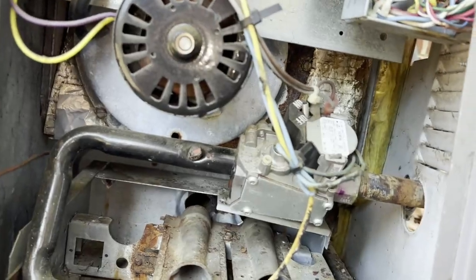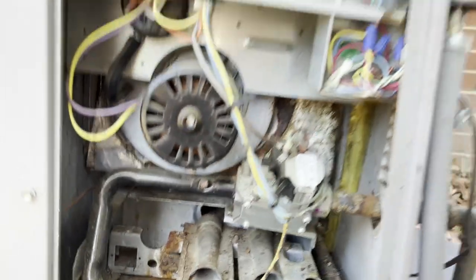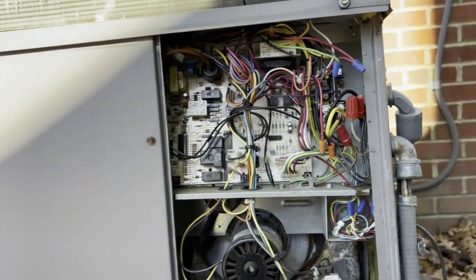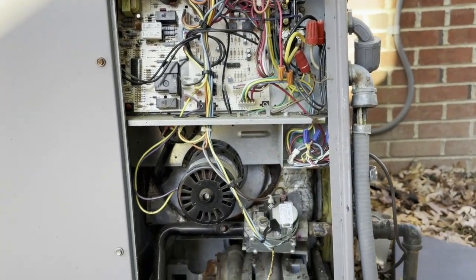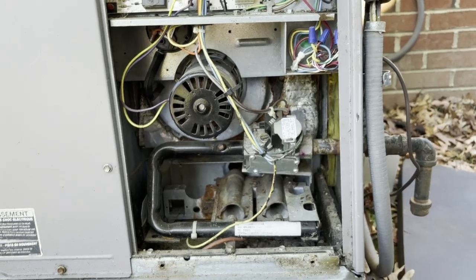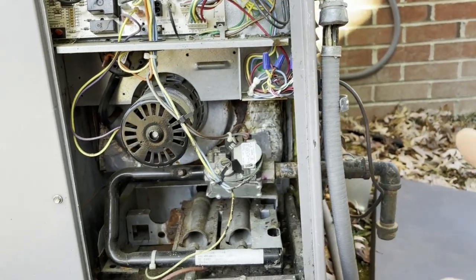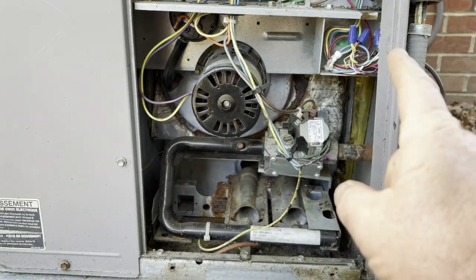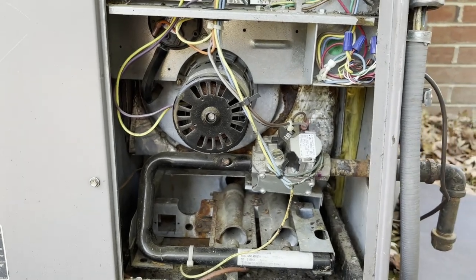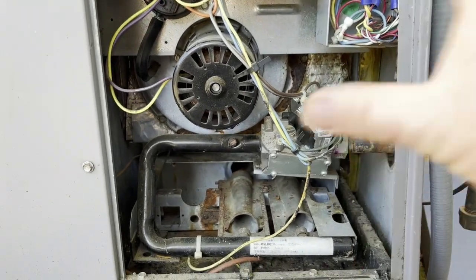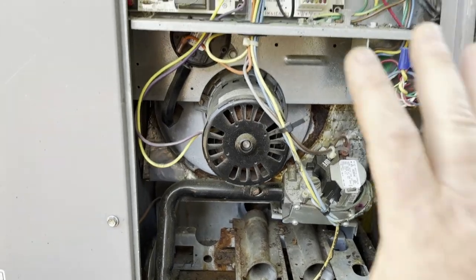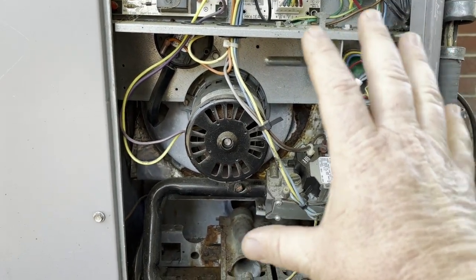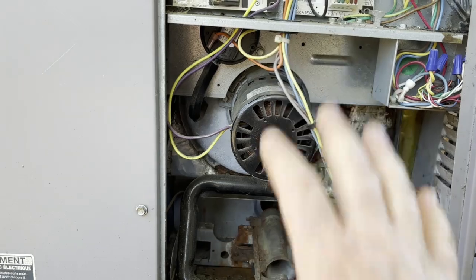So if you ever order a heat exchanger for one of these Carrier ICP style package units, this one's a Payne, Bryant, Carrier, Tempstar, whatever it is, older models, if you order the heat exchanger, always order the flue box cover, the front face panel, front faceplate assembly for it, because that mounts to the actual front of the heat exchanger, and then the draft motor mounts to the front of that.